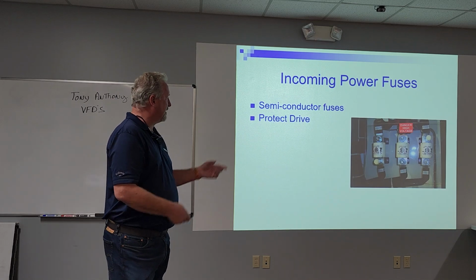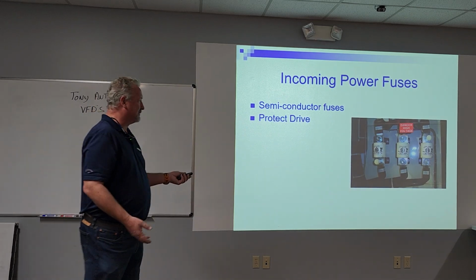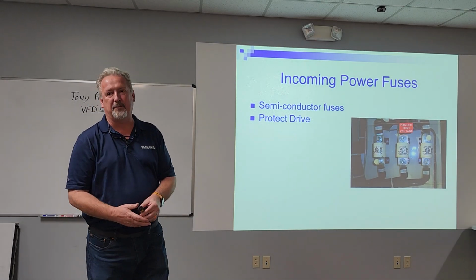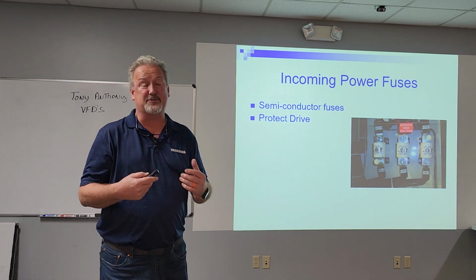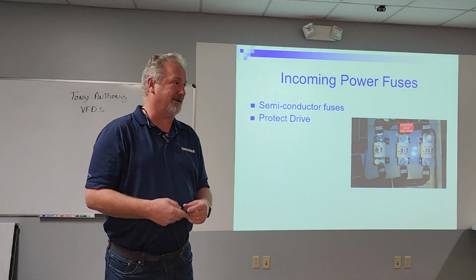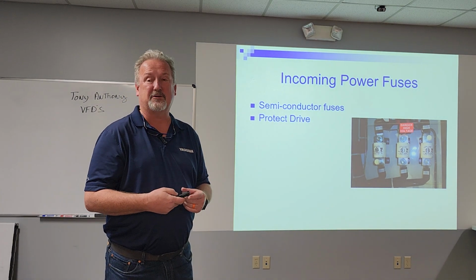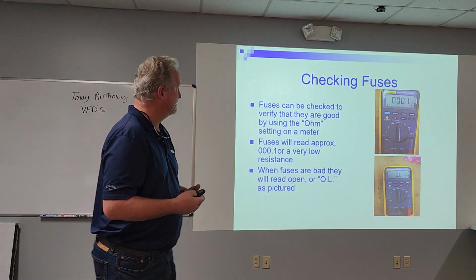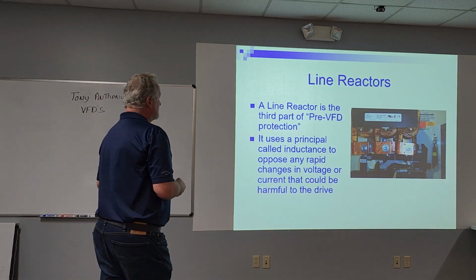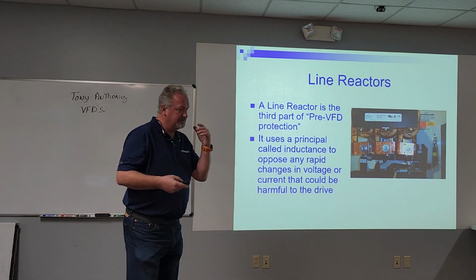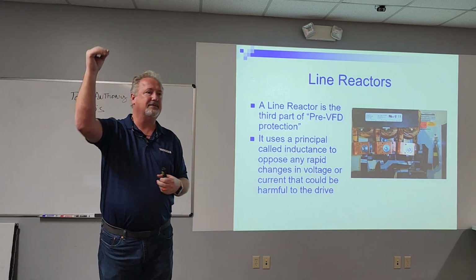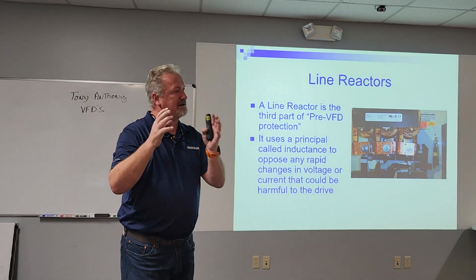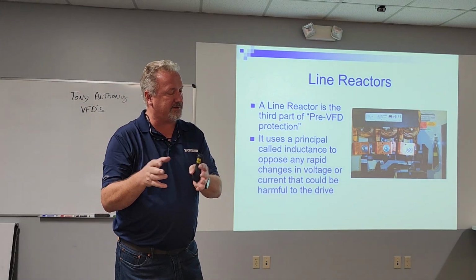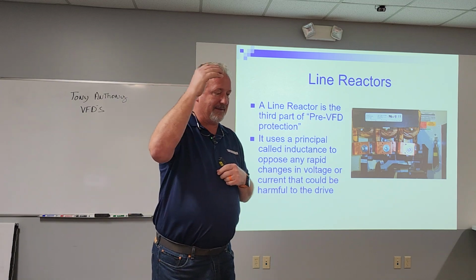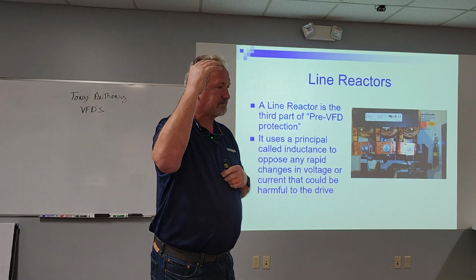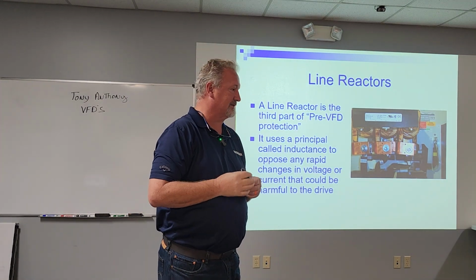And just like with the breakers, the connections, once again, are super important. I'm going to beat that horse a lot, because that is one of the leading causes of electrical equipment failures. So breakers and fuses provide short circuit protection feeding the drive, and they're also what provide a disconnecting means.